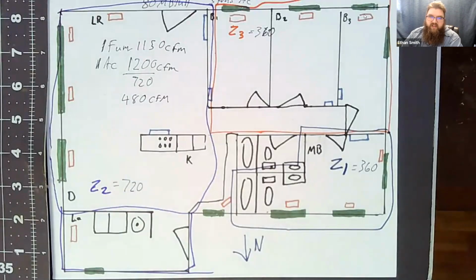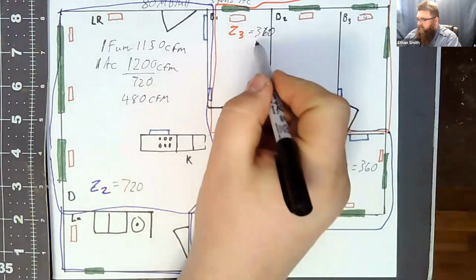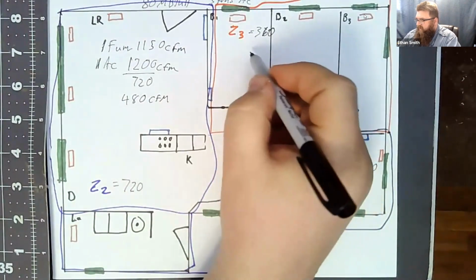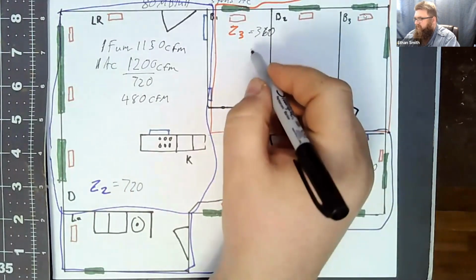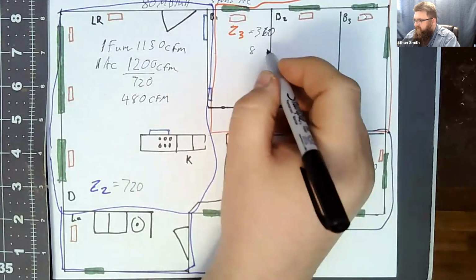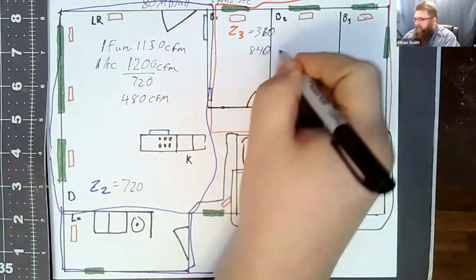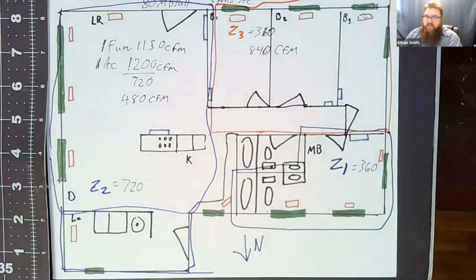Okay, so single stage equipment's probably not a good answer because that's the biggest zone. If we call in one of these other zones, now I have roughly a 840 CFM problem. Okay, that I got to deal with. So we want to minimize excess air. So single stage equipment probably ain't going to work out too well on this zoning plan. Okay, is there any way we could modify this zoning plan to make it work better with single stage equipment?